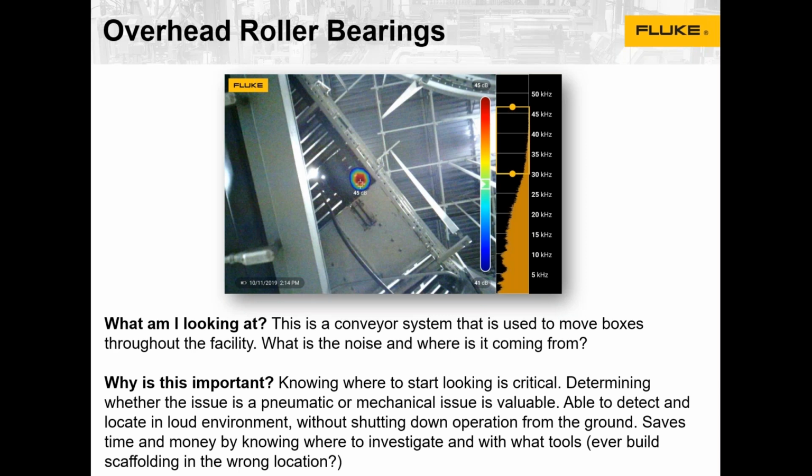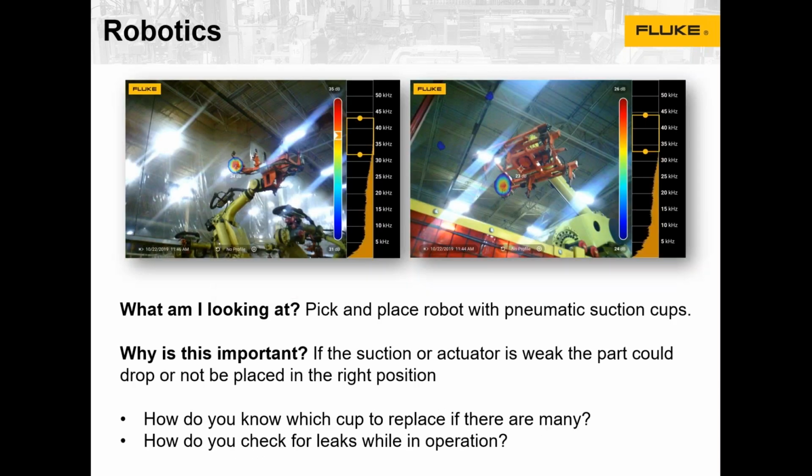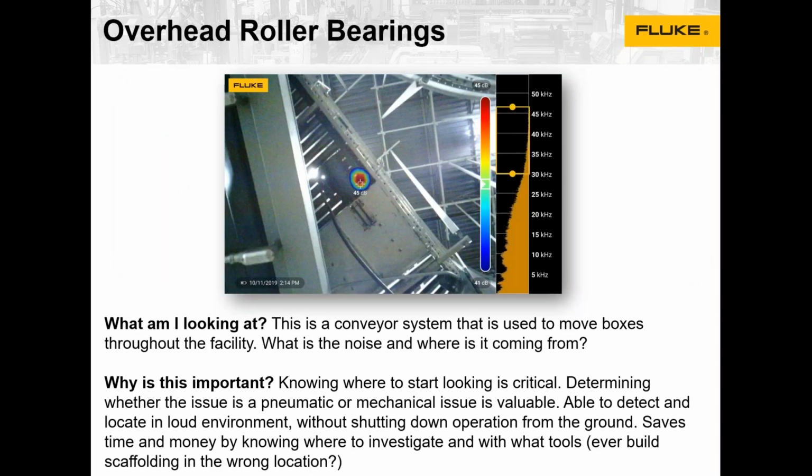Well, and I haven't talked about it much here, where really this is a loud environment. If you're back on the overhead roller bearings, and in all of these situations, you're in a factory and it's loud. But this is loud here, and all the extra sound is eliminated through the algorithm that Fluke has on this device. Yes, you can adjust that frequency, but it's going to eliminate a lot of the background noise, sometimes all of it, like here, even when it's very loud. And yeah, Justin, that's a good point.